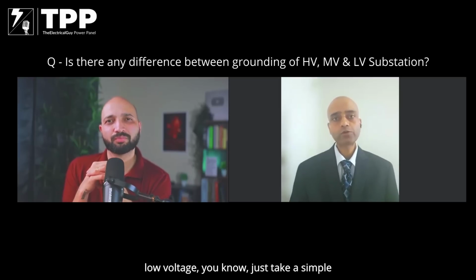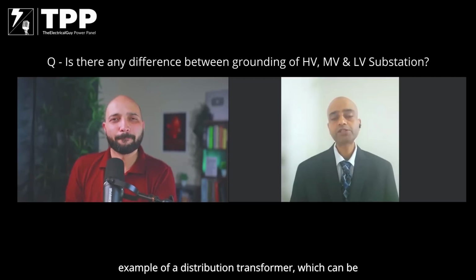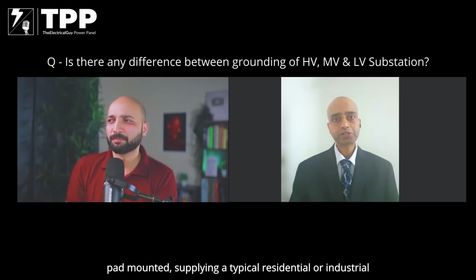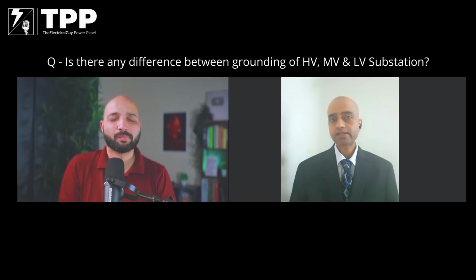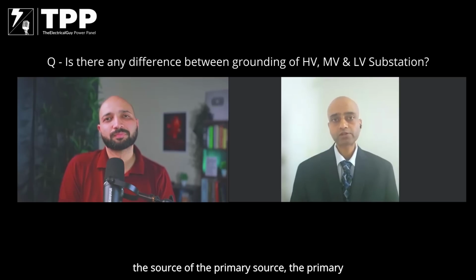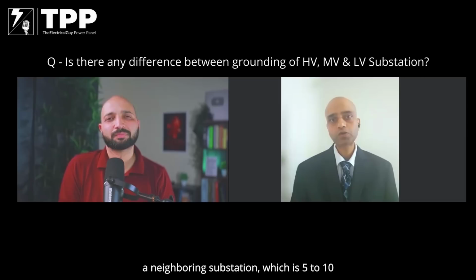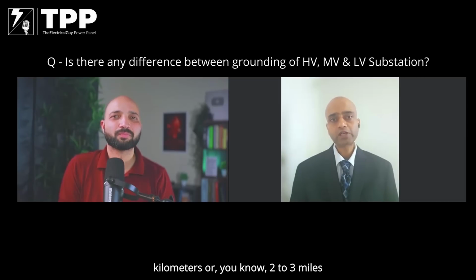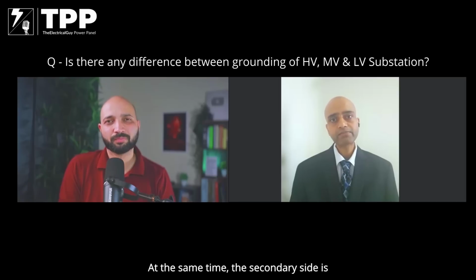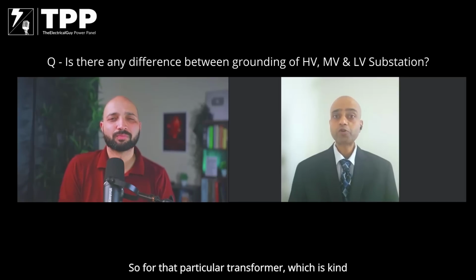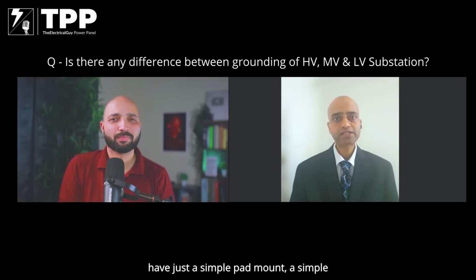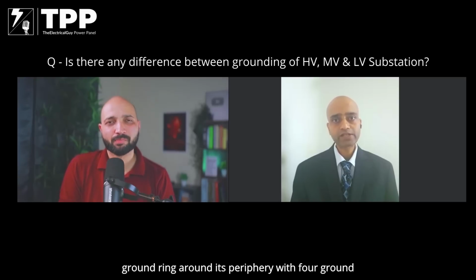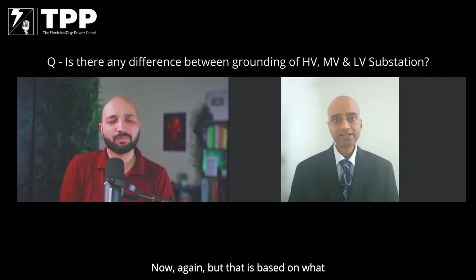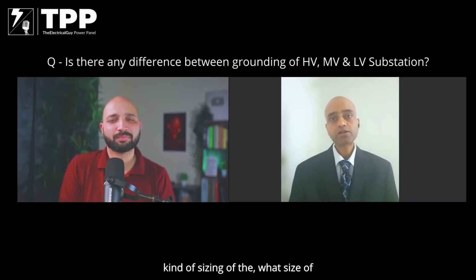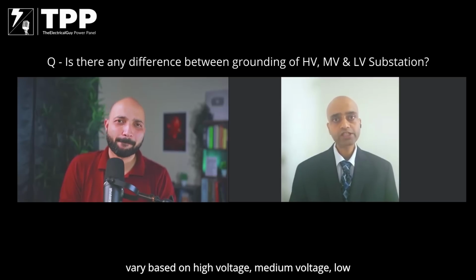And for the low voltage, let's take a simple example of a distribution transformer, which can be pad mounted, supplying a typical residential or industrial load. Again, we don't have any ground grid, and the primary side of the transformer may be connected to a neighboring substation, which is 5 to 10 kilometers, or 2 to 3 miles away. At the same time, the secondary side is supplying the load. So for that particular low voltage transformer, it could have just a simple pad mount, a simple ground ring around its periphery with four ground rods. But that is based on the size of the transformer. So to answer your question, yes, they do vary based on high voltage, medium voltage, low voltage.